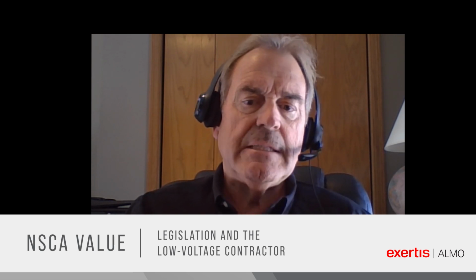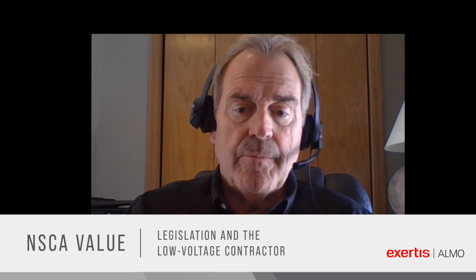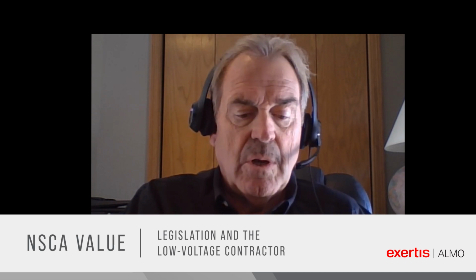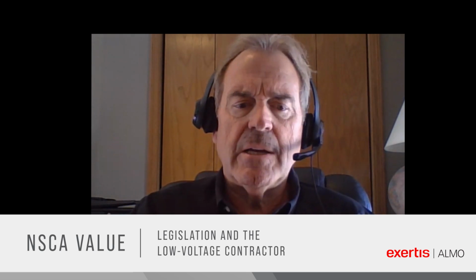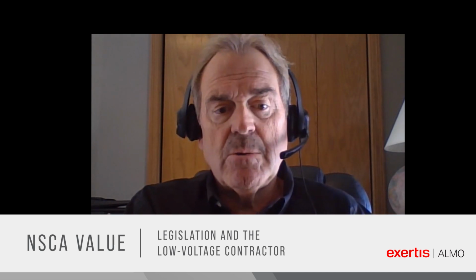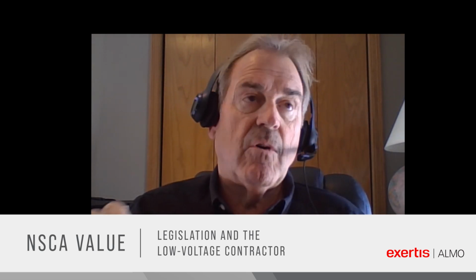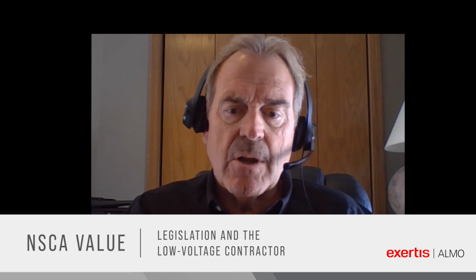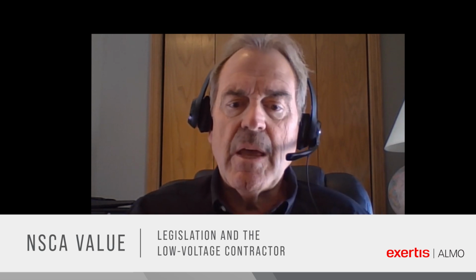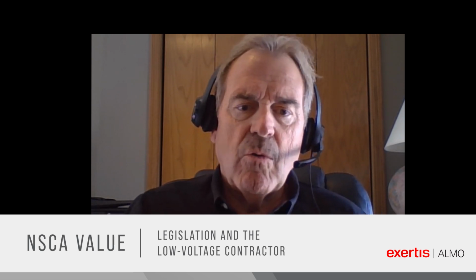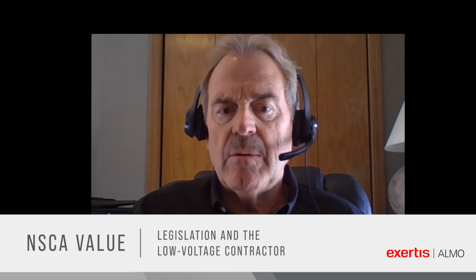So the current NEC defines our work more as class 2 and class 3 circuits. Basically these limited energy circuits are defined within the code to be deemed safe from shock hazards and generating heat that would compromise the insulation or create a fire hazard. So many factors go into it: conductor size, loads, distance, the type of bundling we do. All of it goes into that, and we have all these codes and compliance factors that our committee members meet about, and our code making people who serve on these code making panels help establish what those parameters are. So the low voltage term really isn't relevant compared to the limited energy that we use.